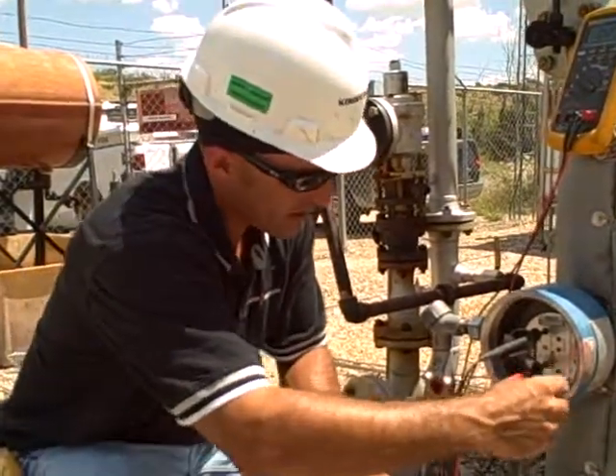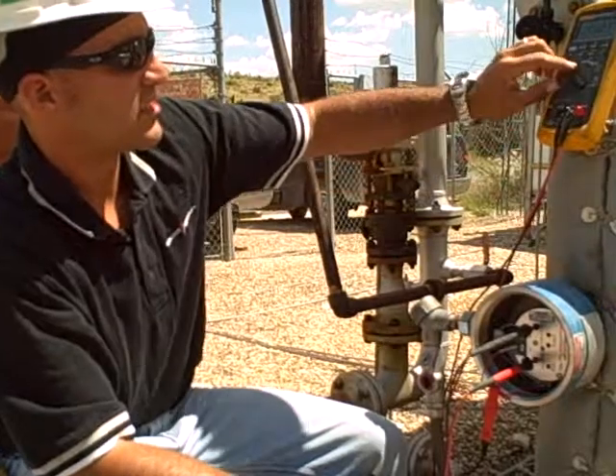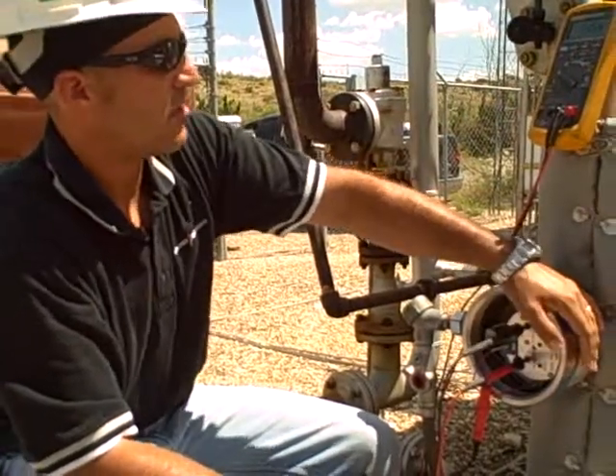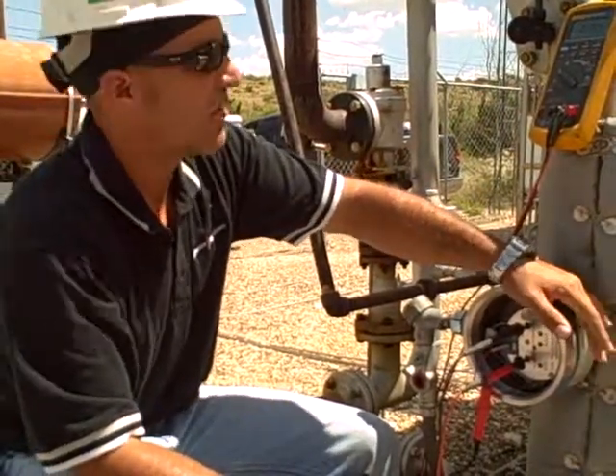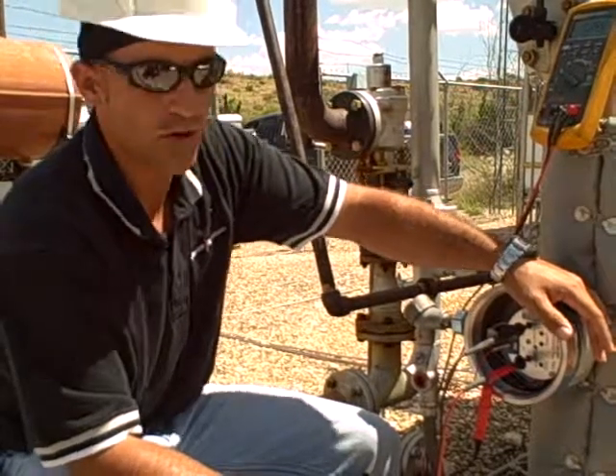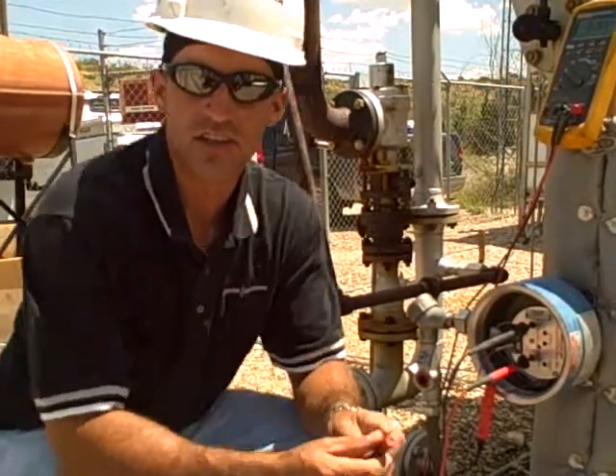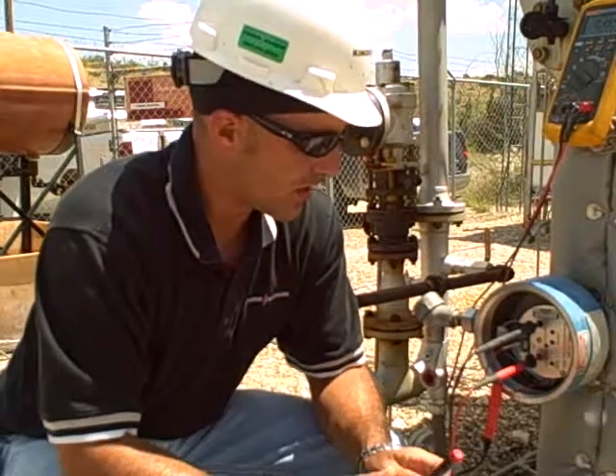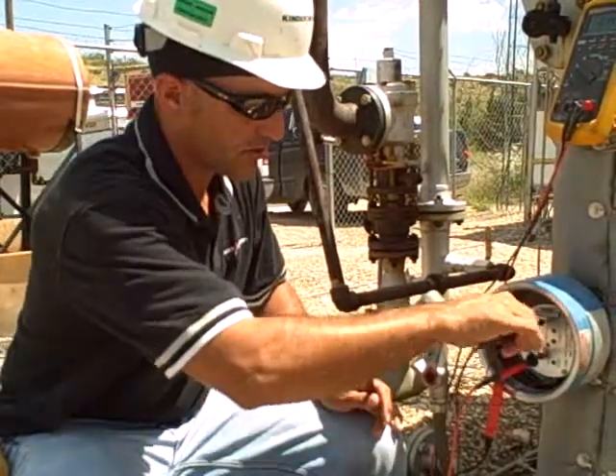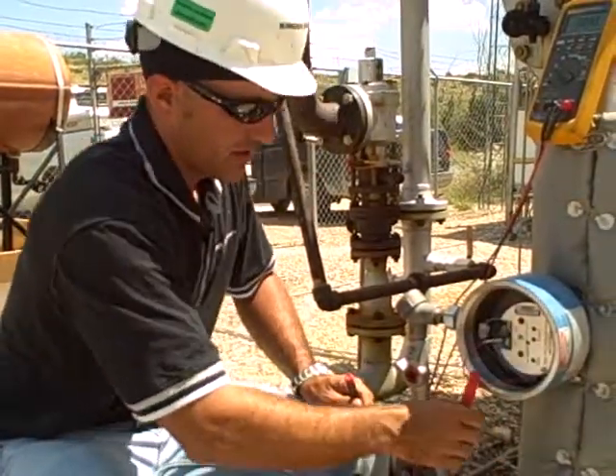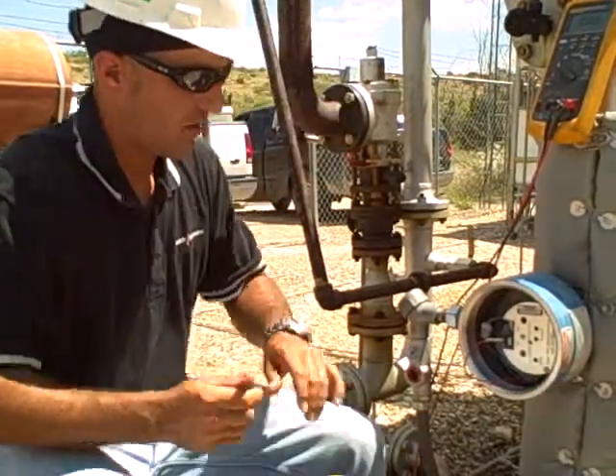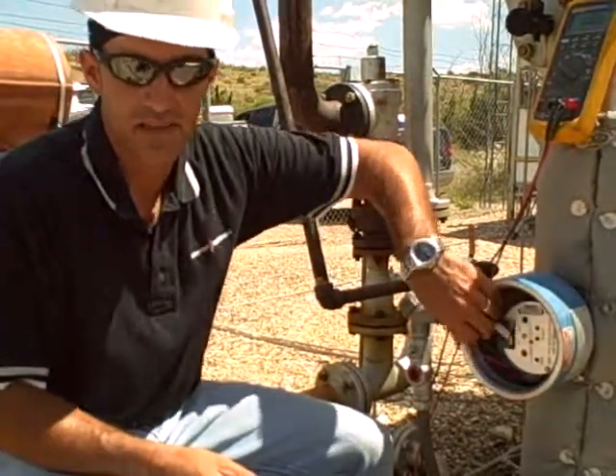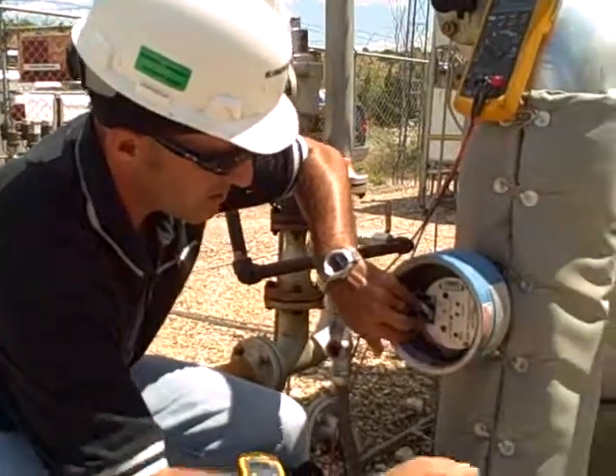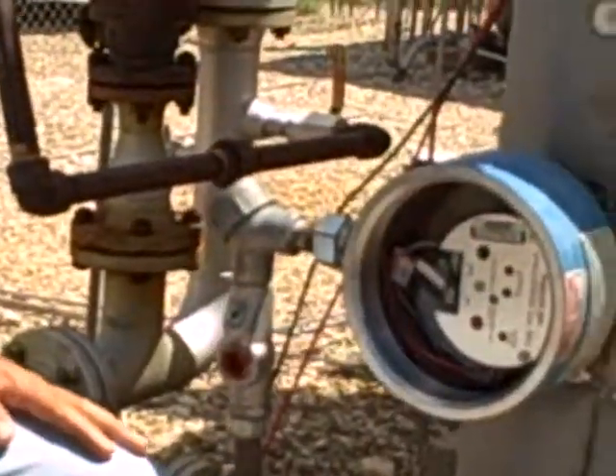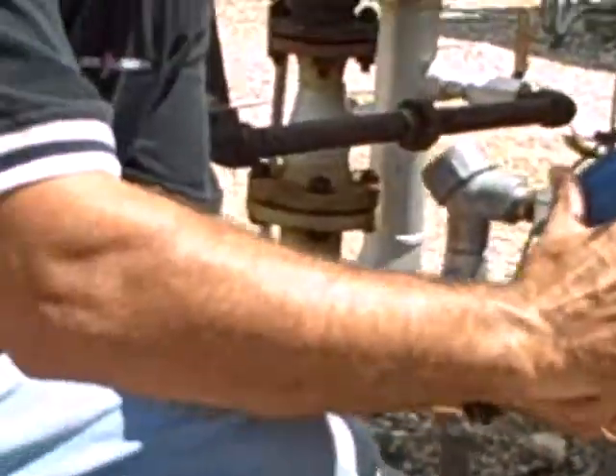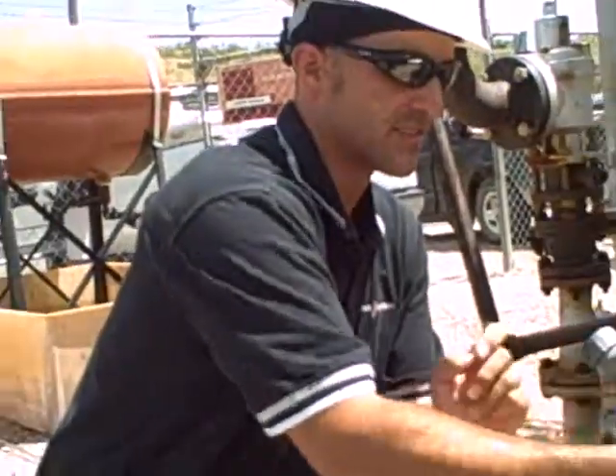Okay, now I'm going to go back to my voltage, and I'm going to look at my lower range only. Okay, and it's 0.152, so it's within the range. Okay, once you're done with that, you're done calibrating it. You can go ahead and disconnect your leads. All right, now before you put the cover back on, you need to make sure that this toggle switch is in reference. And we'll go ahead and put the cover back on, make sure it's nice and tight.